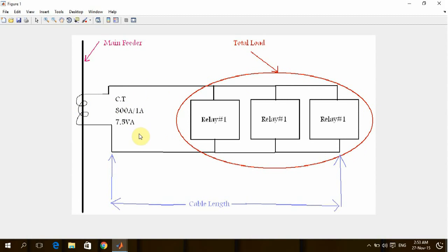We have to make sure that the whole burden or load connected to this CT, in addition to the burden of the cable itself which will connect the CT with the relay, is not reaching the CT maximum burden which the CT can deliver.